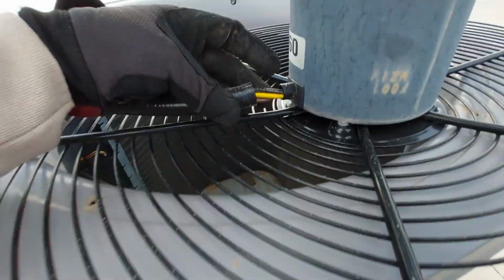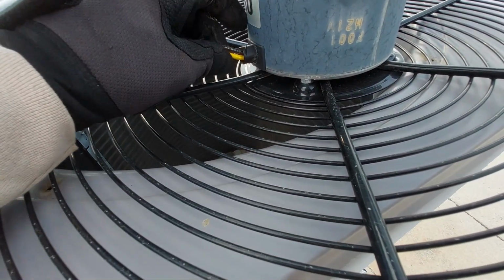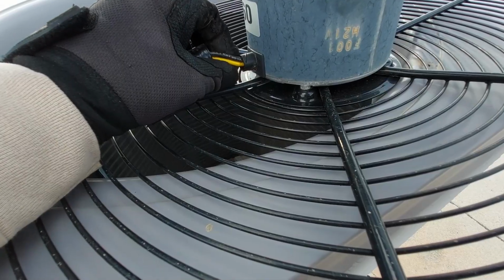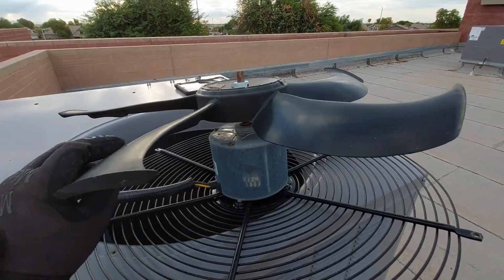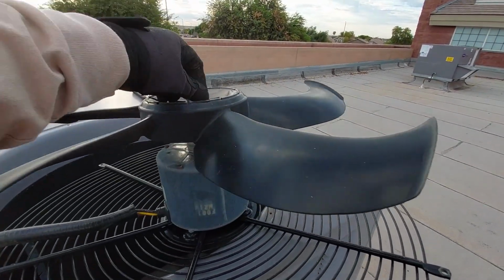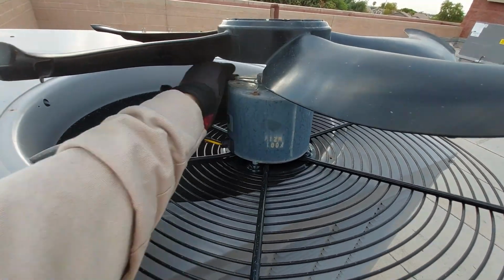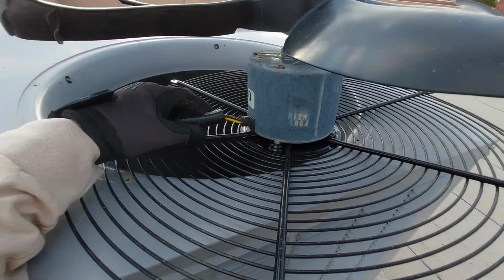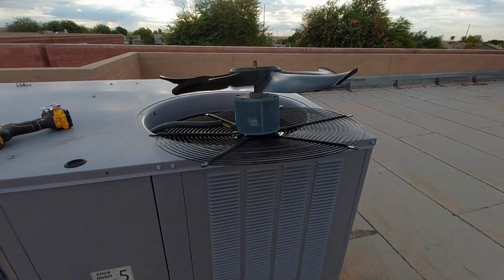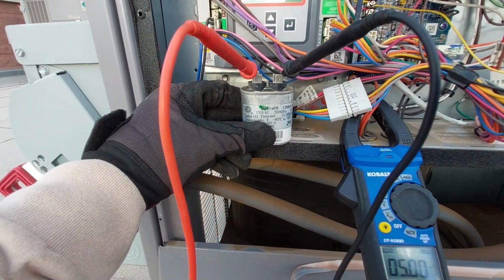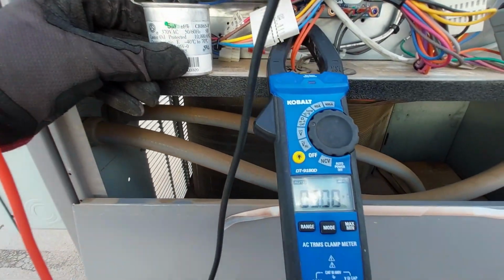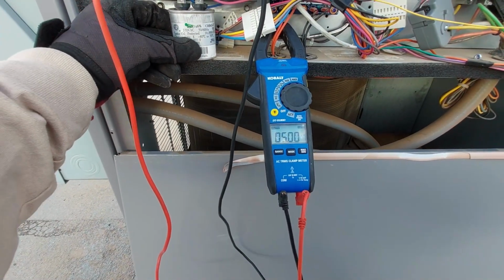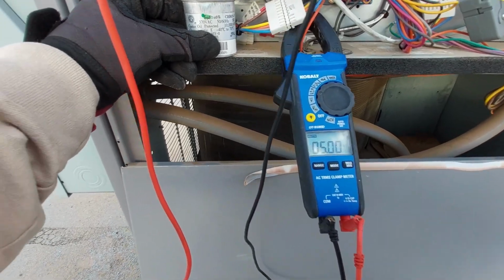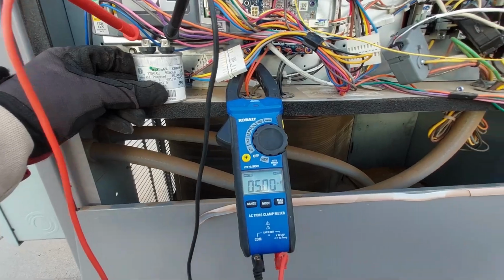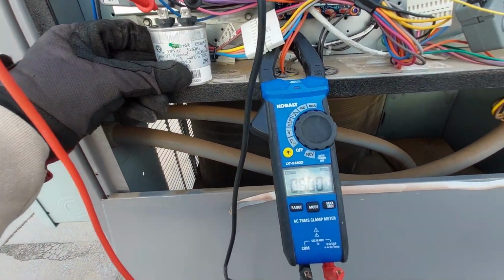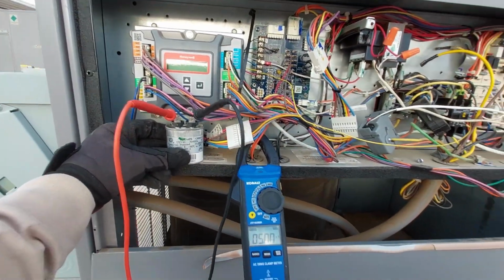Alright, so check it out. I got black, yellow, and brown. So black and yellow, high voltage. Brown goes to my capacitor. But it doesn't feel like the shaft is bad. The condenser fan motor isn't even hot. So this capacitor for the condenser fan motor is 5 microfarads. I'm getting 5.00, which is probably one of the best capacitors I've ever seen. I've never seen one that close to the actual microfarads, which is a little suspicious if I'm being honest. But I mean, it's doing its job. Well, not really, because that condenser fan motor is not running.